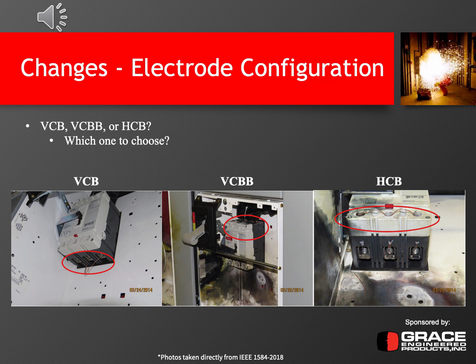So again, which one do you choose? The best way is to choose all three and calculate for all three, which is why the use of commercial software is very beneficial and helpful in this sense, to speed up some of these arc flash studies, because that's a number of calculations you can do at thousands of different points in the system.